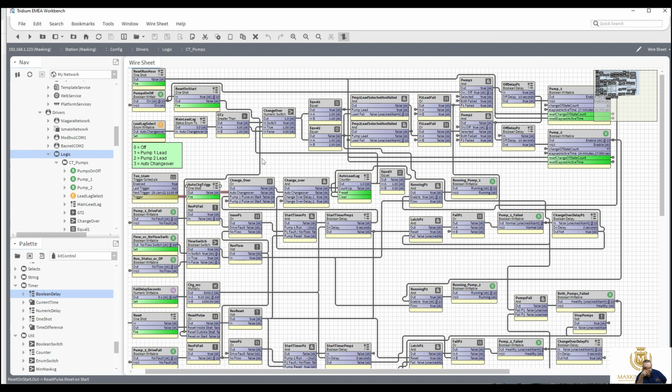So that's going to stop any interference, i.e. the plant is not going to see the pumps stopped and start throwing out alarms, because we're running both pumps at the same time, only for a brief 10 seconds, but then we can use that logic for boilers, that we can turn off the pumps. So basically this pumps on and off here.